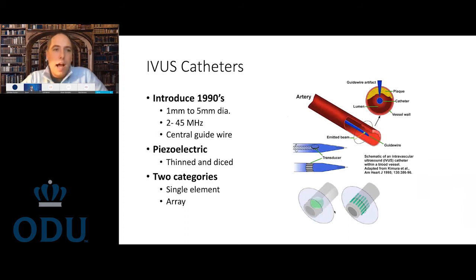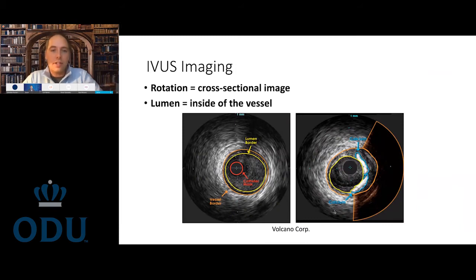Along come these IVUS catheters, introduced in the 1990s, usually about 1 to 5 millimeters in diameter. They're all piezoelectric based, with transducer elements that are thinned, diced, and placed around a catheter. They're extremely small, and typically you're looking at the sidewall. They'll go up through the arteries and veins, usually through the femoral artery, rotate around quite often to get a view of the side, and retract at a known rate so you can come up with a 3D image or a cross-section. Unfortunately, you don't have the ability to look in front of you as you're going, and that can lead to problems like puncturing the sidewall.